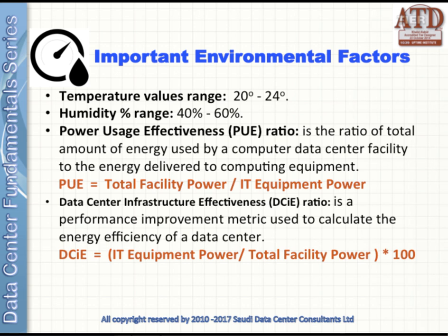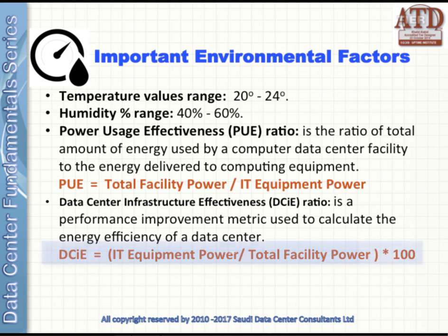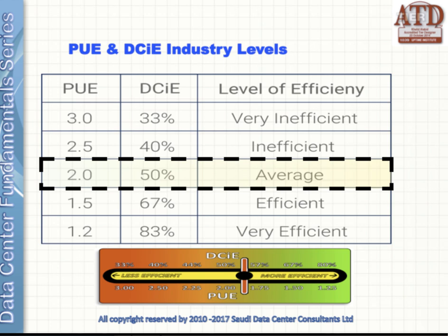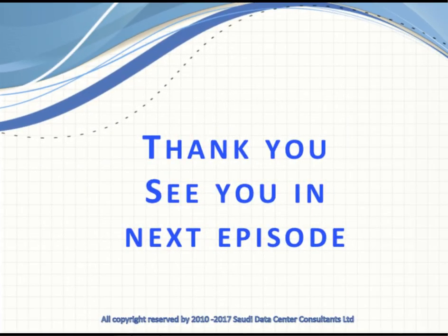You should pay attention to the following environmental factors: temperature, with a value range of 20 to 24 degrees Celsius; humidity percentage, which should be between 40 to 60 percent. Recently, PUE ratio has become an important measure for data center power efficiency, as it measures total power consumed by the facility to total power delivered to the data room. Finally, DCIE can be calculated to measure the energy efficiency of the data center. In this table you can see the industry standard levels for those factors — the aim is to be as efficient as possible. Thank you for watching and see you in the next episode.